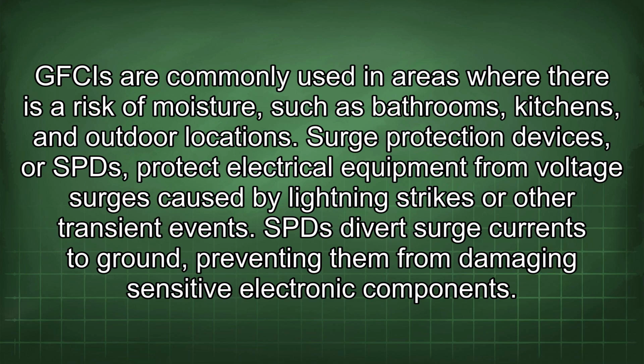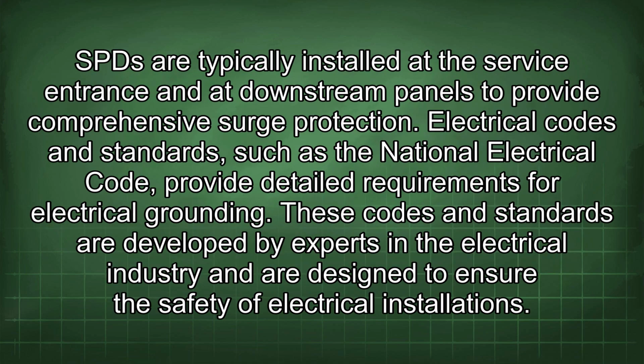Surge protection devices, or SPDs, protect electrical equipment from voltage surges caused by lightning strikes or other transient events. SPDs divert surge currents to ground, preventing them from damaging sensitive electronic components. SPDs are typically installed at the service entrance and downstream panels to provide comprehensive surge protection.